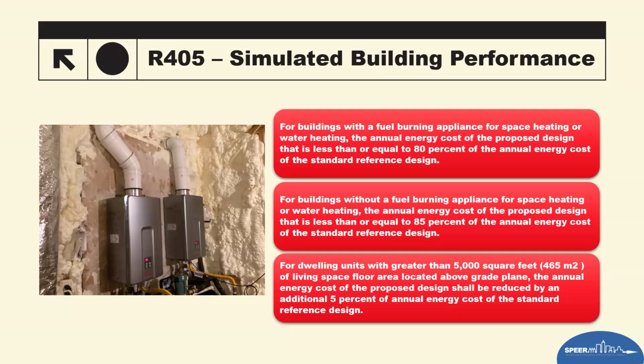They're starting to do what most people would call penalizing a large building. So for anything over 5,000 square feet, the code now requires an additional 5% reduction. So if you're using fuel burning appliances, it's no longer a 20% reduction, it's a 25% reduction. You're adding that additional 5%. This accounts for the overall energy impact. In short, of course, the building performance path doesn't just look at insulation and equipment.